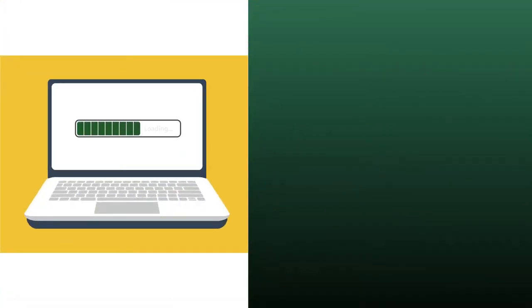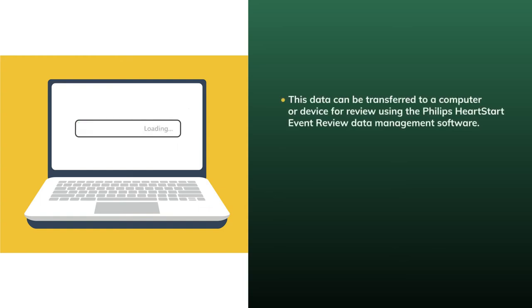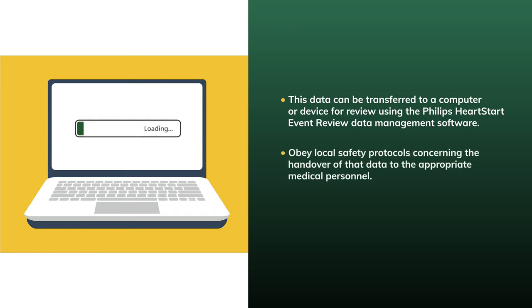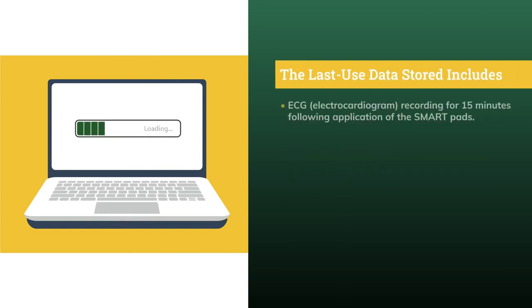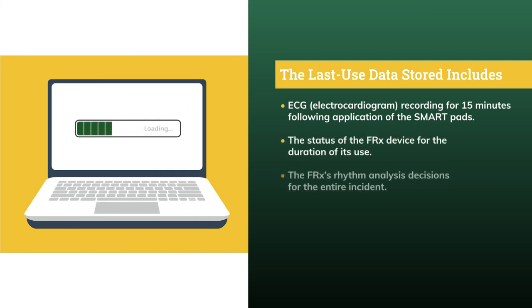The HeartStart FRx AED stores data automatically for 30 days following its last use. This data can be transferred to a computer or device for review using the Philips HeartStart Event Review data management software. Obey local safety protocols concerning the handover of that data to the appropriate medical personnel. The last use data stored includes ECG recording for 15 minutes following application of the smart pads, the status of the FRx device for the duration of its use, the FRx's rhythm analysis decisions for the entire incident, along with the elapsed time associated with the entire event.